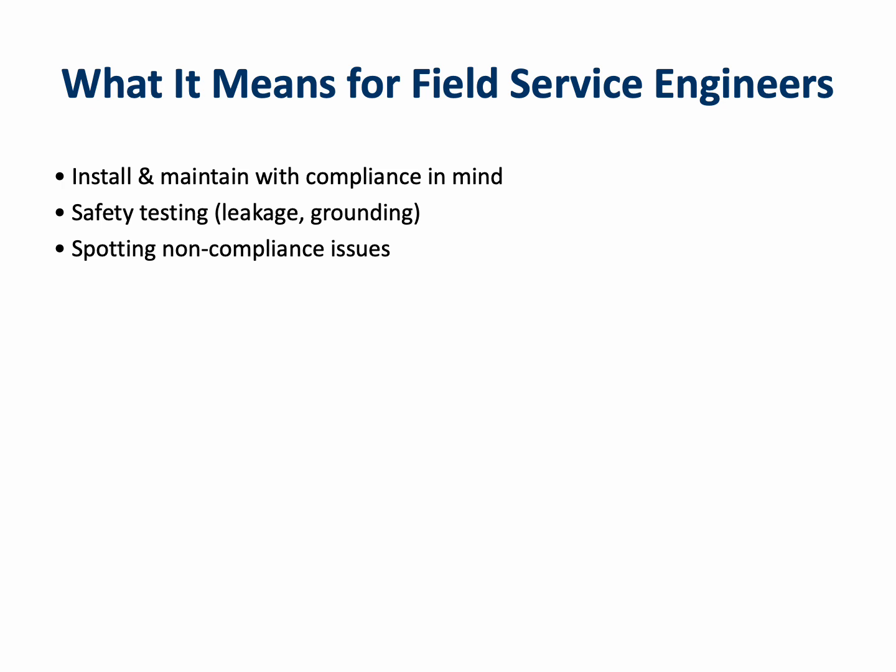What does it mean for us as field service engineers? So when we install, maintain, or repair equipment, we're not just fixing a machine. We're making sure it continues to meet the IEC 60601 standard. That means testing the leakage currents, checking the grounding, and spotting risks that could actually remove the device out of compliance.